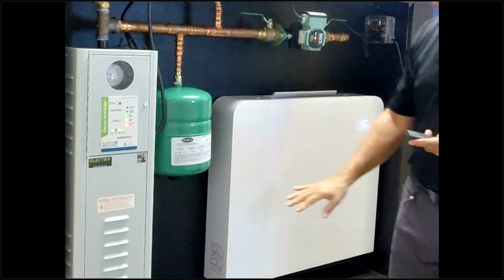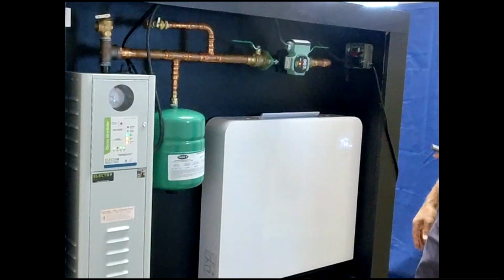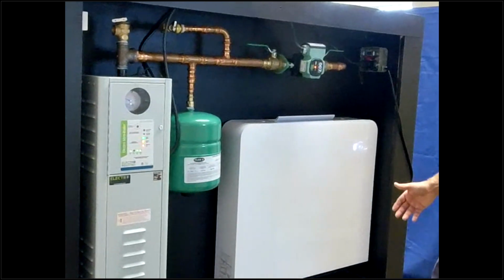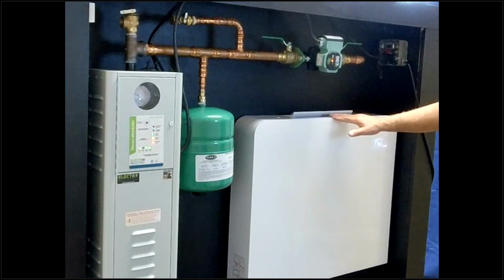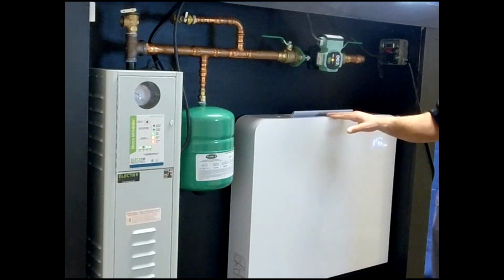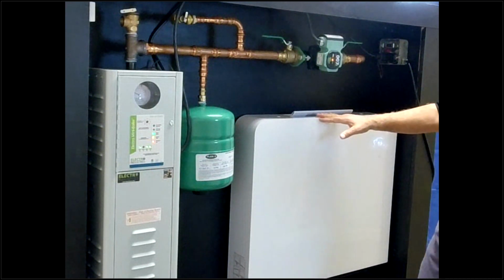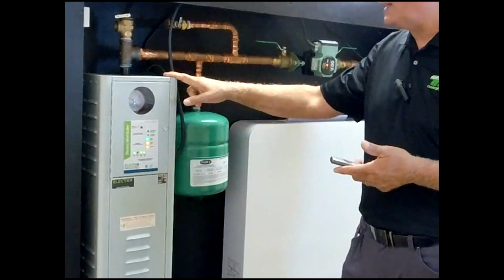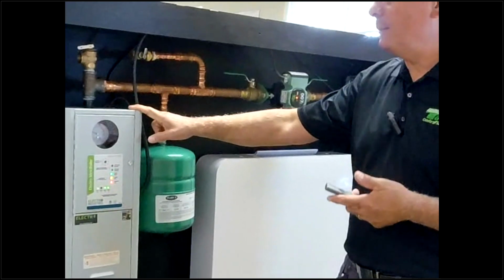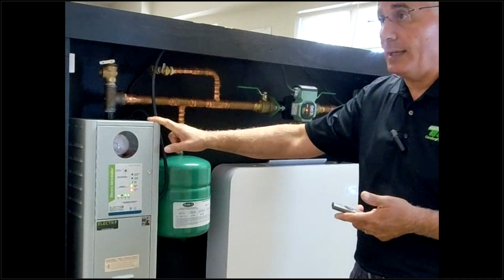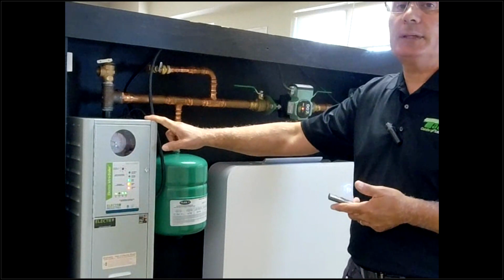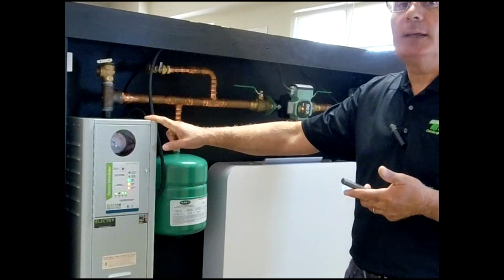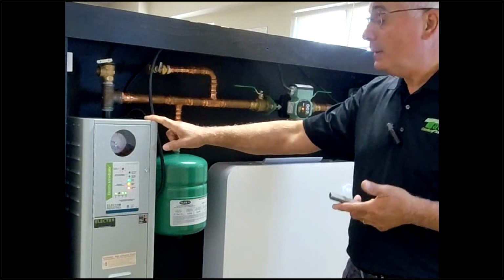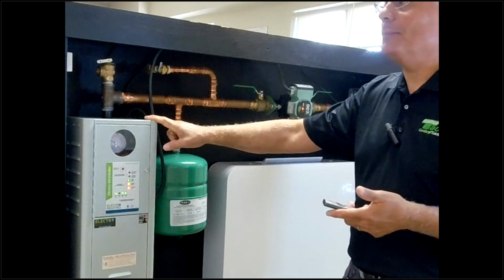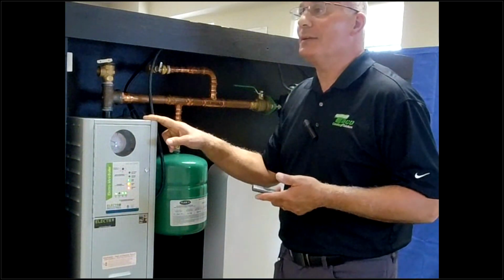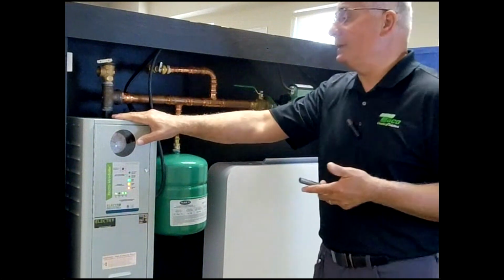So what we're showing here is a very compact, just single zone situation, and we're using electricity here and a hydronic coil that you can put room by room as your delivery system. I think this is really cool. I think this is going to be a future item in the world of hydronics. So unless we come up with an alternative fuel source to natural gas or propane, an electric boiler is going to be a very, very good option going forward. All right. If I'm still in my house when my boiler has to be replaced, I am going to replace it with an electric boiler. You may be saying, well, what's the amount of wattage?